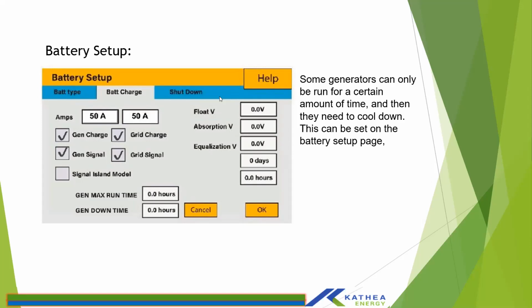So when setting battery charge, please take note of your peak loads, usually in an off-grid scenario, how much peak power you use, and then you calculate the equivalent in current, such that you won't overload your generator when it's charging your battery and supplying the loads at the same time.